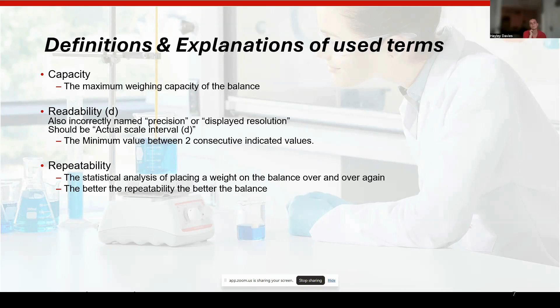The accuracy of the weights is actually defined by their class. So you've got anything from E1, E2, F1, all the way down to M1, M2, and M3. And these M class weights, the M1, M2, M3, are essentially the ones that would be more suitable for use in the classroom setting. The E2, the E1, the F1 weights are more for the higher end, semi-micro, analytical balances.